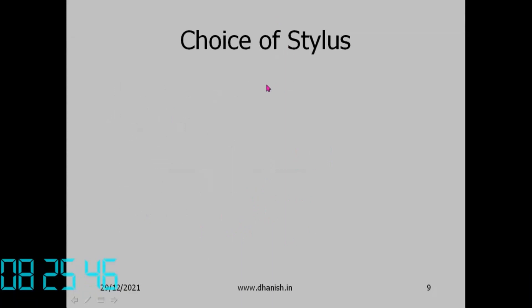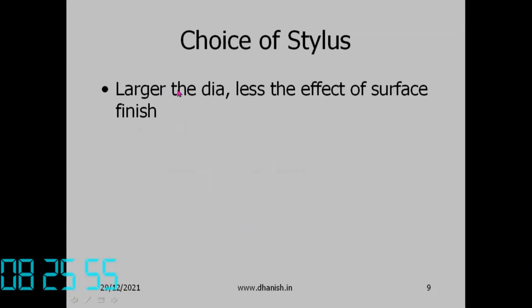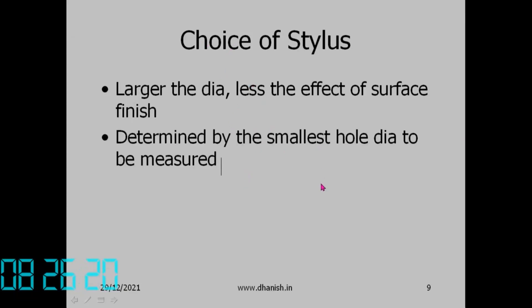For stylus choice, stylus diameter and extension length must be selected. A larger diameter reduces the effect of surface finish — it filters out roughness. However, the stylus must be smaller than the smallest hole to be measured. We should avoid changing the stylus as much as possible, since each change increases uncertainty.